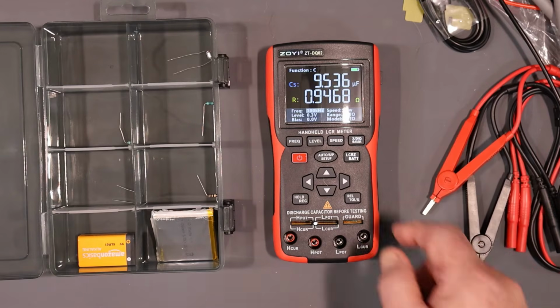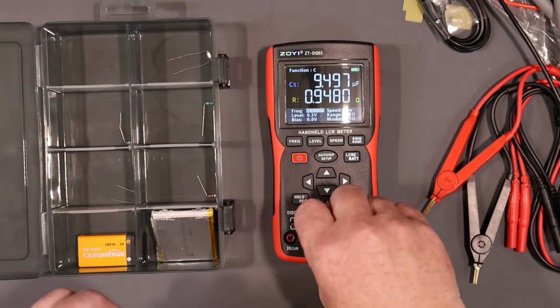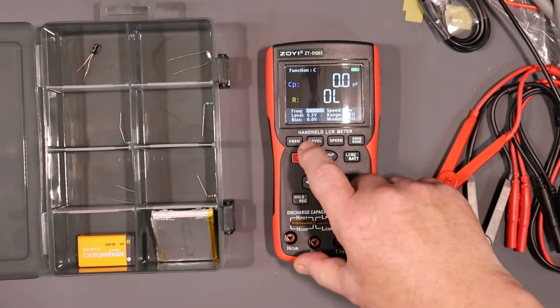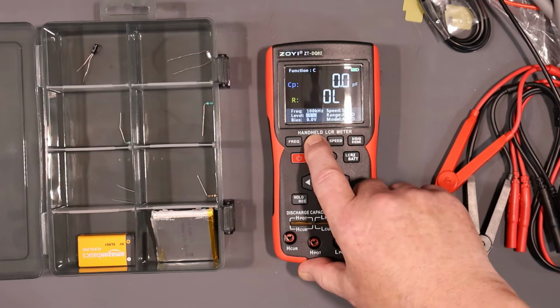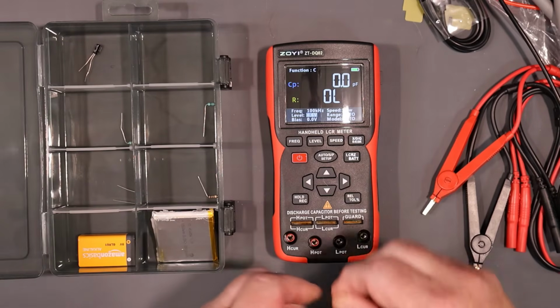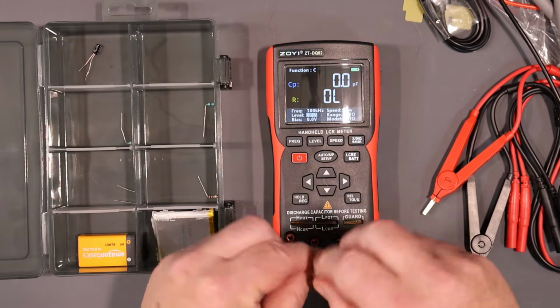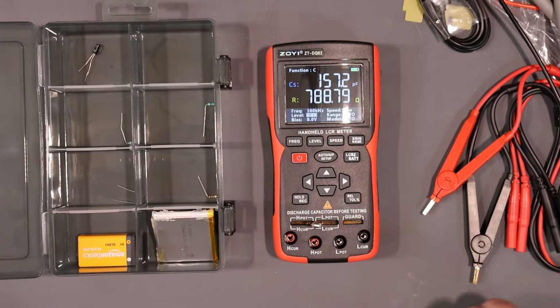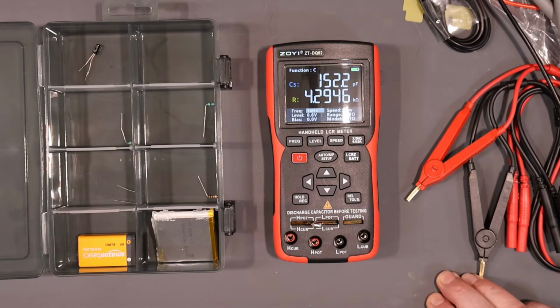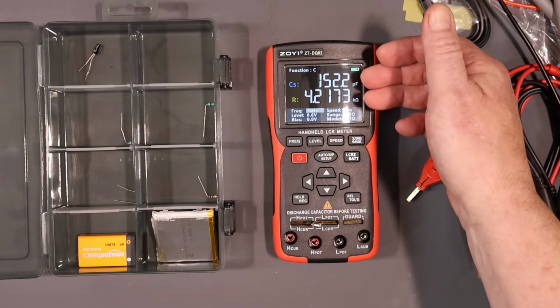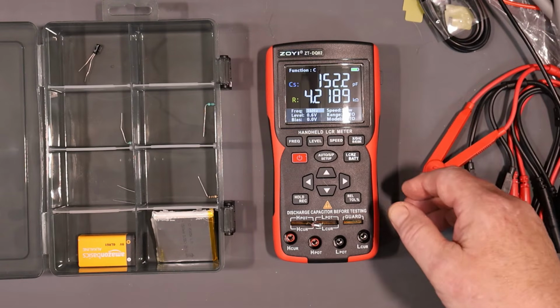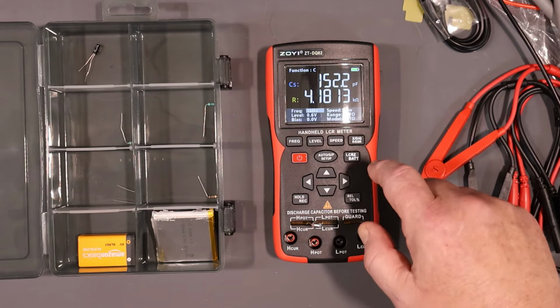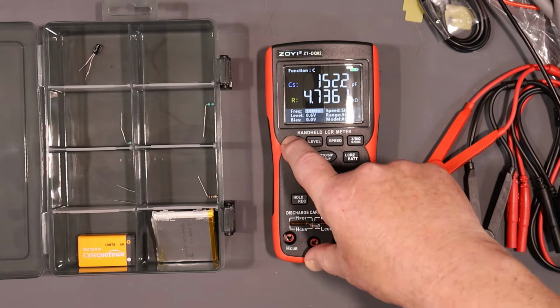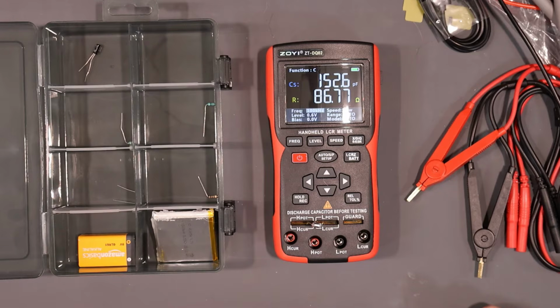All right, let's move on to the other capacitor. We'll take this out and put the level at 0.6. This one's got very delicate little leads in it - let's see if I can get them in there. And I can. The East tester measures this at 149.5 and we're at 152, so well within the 3%. We'll bring it up now to 100 kilohertz, and East tester measured it also at 149.9. Again, we're right on here.